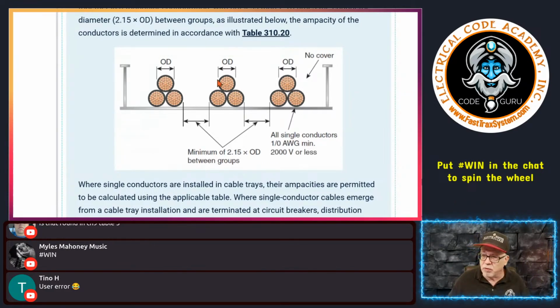Well, what it's saying is, if it's in a triad or quad, you take the largest conductor in the configuration and you multiply 2.15 times the OD, whatever this is. You can get this from Chapter 9, Table 5. If it's larger, you can get it from the manufacturer's product sheets, whatever you get, and you do the calculation. 2.15 times the OD, that is the space that you have to have before you put your next configuration in.